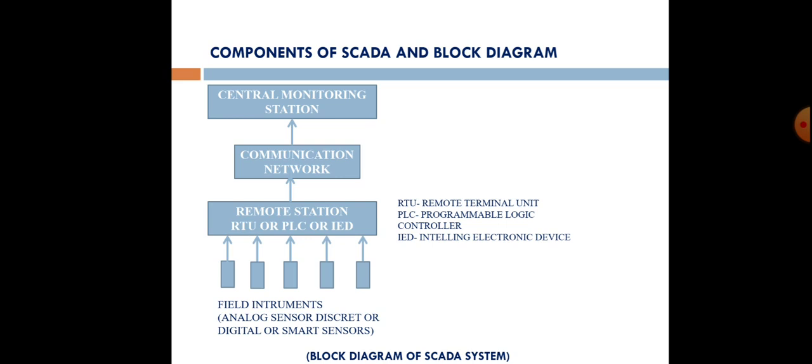Analog type sensors convert physical parameters like fluid flow, velocity, fluid level, temperature, pressure into analog electrical signals. In this, 0 to 5 volt, 1 to 5 volt, 4 to 20 milliampere, 0 to 20 milliampere are the industrial standards. Current type signals are employed as less error is produced when the signal has to be transmitted over a long distance.